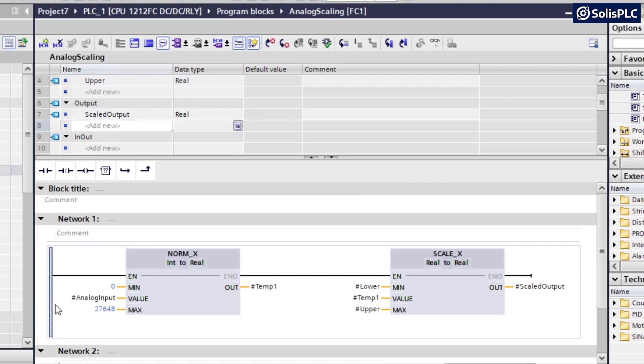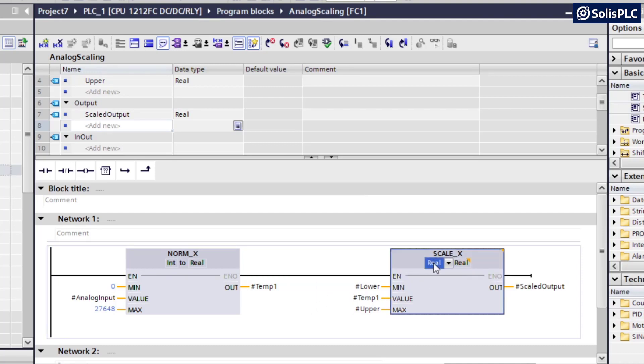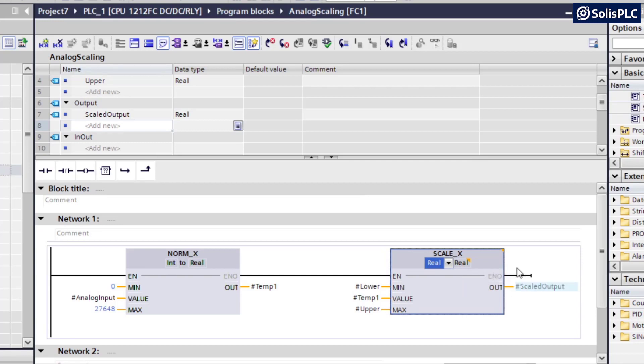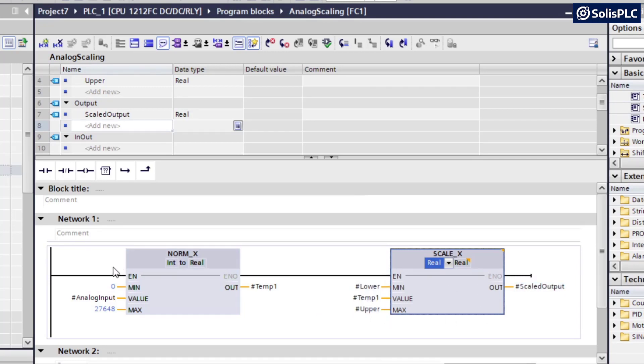So everything looks good. This is our implementation of the function. What's important to check is that you're always scaling, in this case, from real to real. It's possible to get the data types wrong. In that case, if you're scaling to an integer, that's going to be specified from 0 to 10, you're going to lose a lot of data.